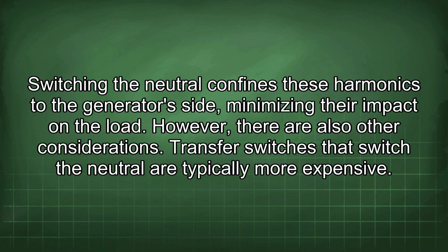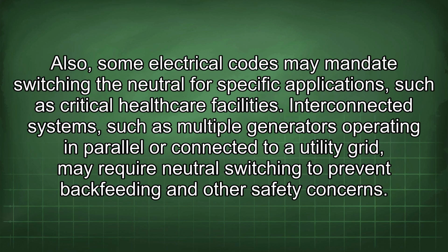However, there are also other considerations. Transfer switches that switch the neutral are typically more expensive. Also, some electrical codes may mandate switching the neutral for specific applications, such as critical healthcare facilities. Interconnected systems, such as multiple generators operating in parallel or connected to a utility grid, may require neutral switching to prevent backfeeding and other safety concerns.